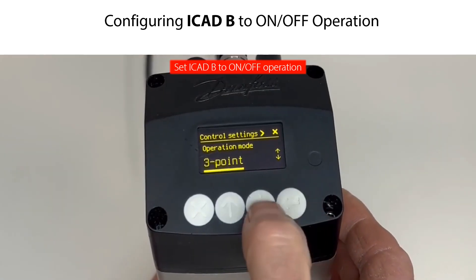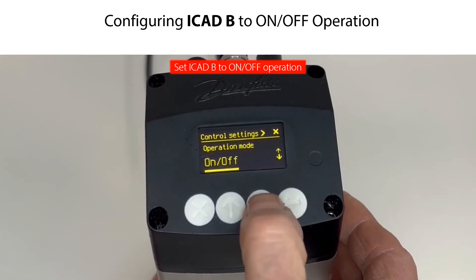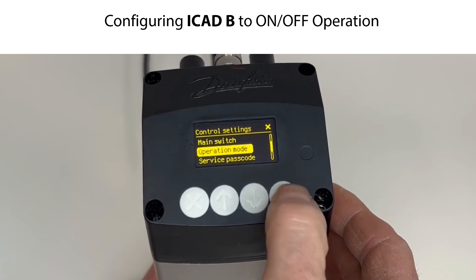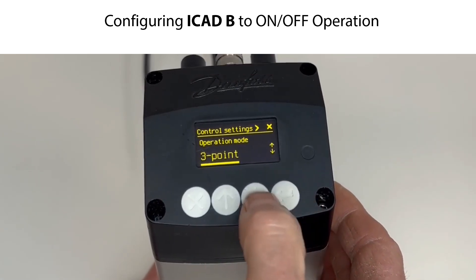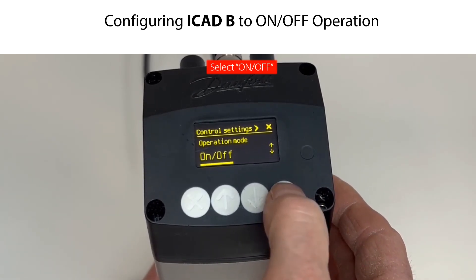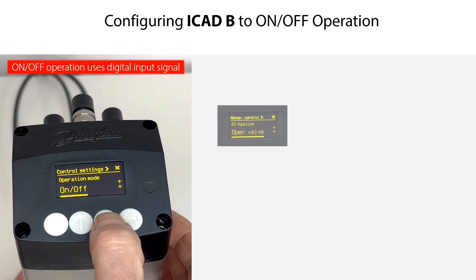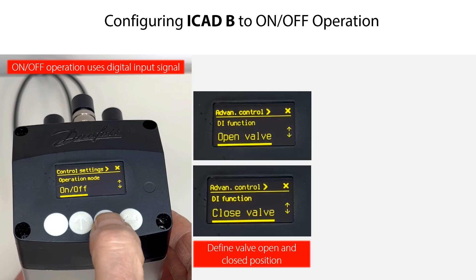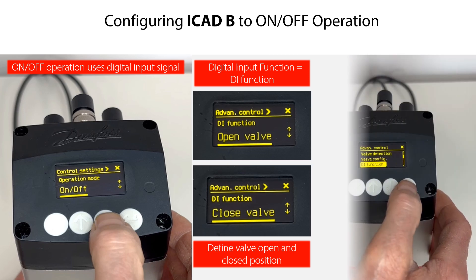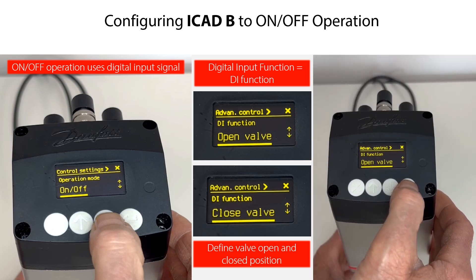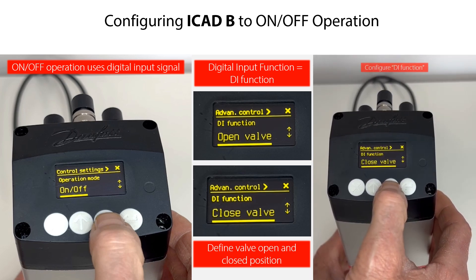Let us now configure the ICAD-B to On-Off Operation. Scroll down to Operation Mode, then press Enter. Select On-Off, then press Enter and Exit. Please note that the On-Off Operation Mode is based on a Digital Input Signal, where the open and closed position of the valve needs to be defined. This is called the Digital Input Function, or simply DI Function. Therefore, you might also need to configure this in the ICAD-B.